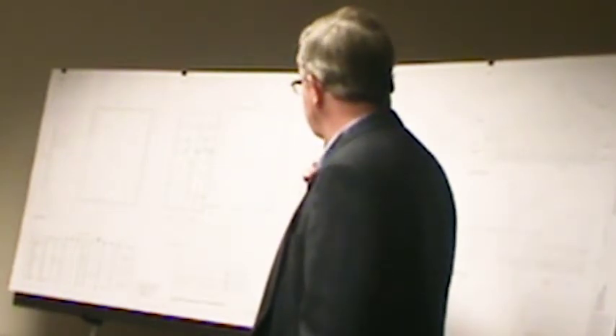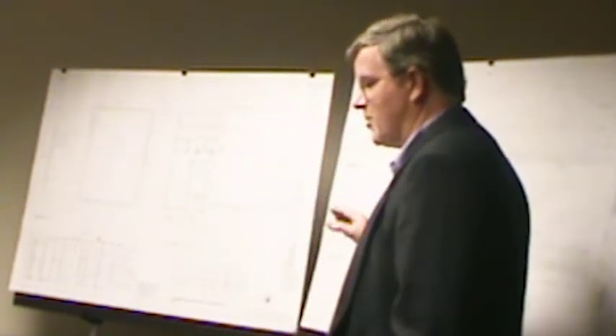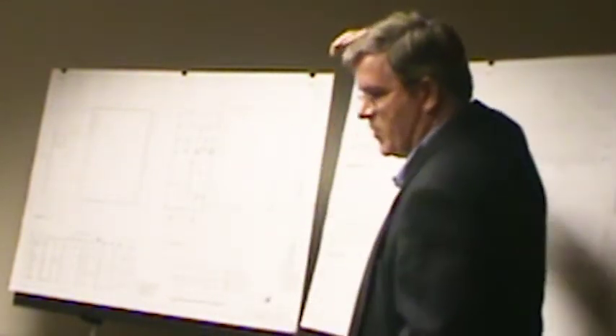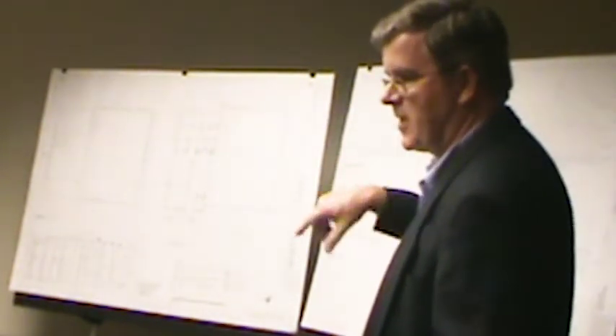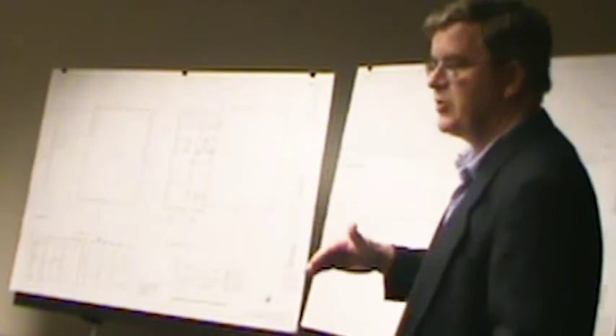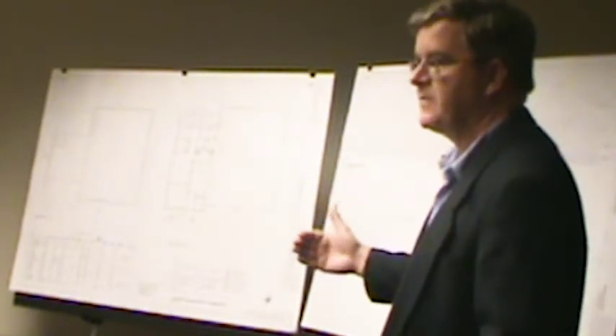We are designing, for instance, this hydronic heating system so that you can maintain lower temperatures overall, because the temperature you want is down here at your feet, and you're not necessarily concerned with what's above. We do have de-stratification fans above, so in the summertime you get that reverse effect. We didn't look at solar basically because we have a reasonably tight budget. We're not trying to over-design and over-build this facility. So we don't have that.